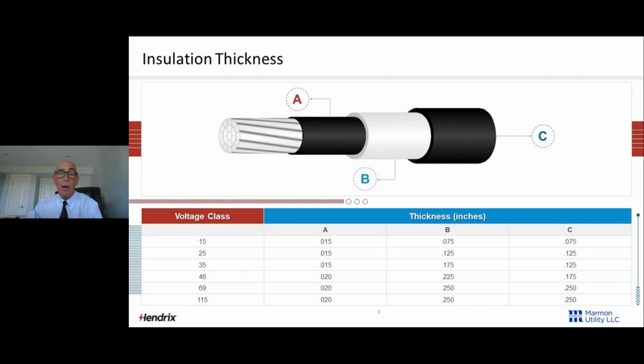And of course, by Ohm's law, if we have higher voltages and we want to keep the current down to 1/3 or maybe 1 milliamp of the higher voltages, we're going to have more insulation. So you can see at 15 kV, the two layers, the A is the semicon, the B and the C are the inner and the outer layers. You can see at 15 kV, we have 75 plus 75 mils, 150 mils, which is about 3.6 millimeters. Meanwhile, when we get to 69 and 115, we've got 250 plus 250. We have 500 mils, which is essentially a ½ inch, or about 12.5 millimeters.